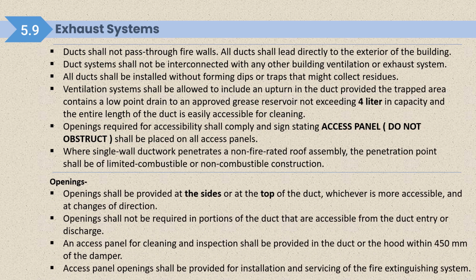Opening shall be provided at the side or at the top of the duct. It should not be provided at the bottom. So we should always remember that whenever we are providing the access door, access panel, it should be on the side or at the top of the duct, whichever is more accessible, and at change of direction. Opening shall not be required in portions of the duct that are accessible from the duct entry or discharge. So at duct entry or duct discharge, you don't need to provide the access panel.